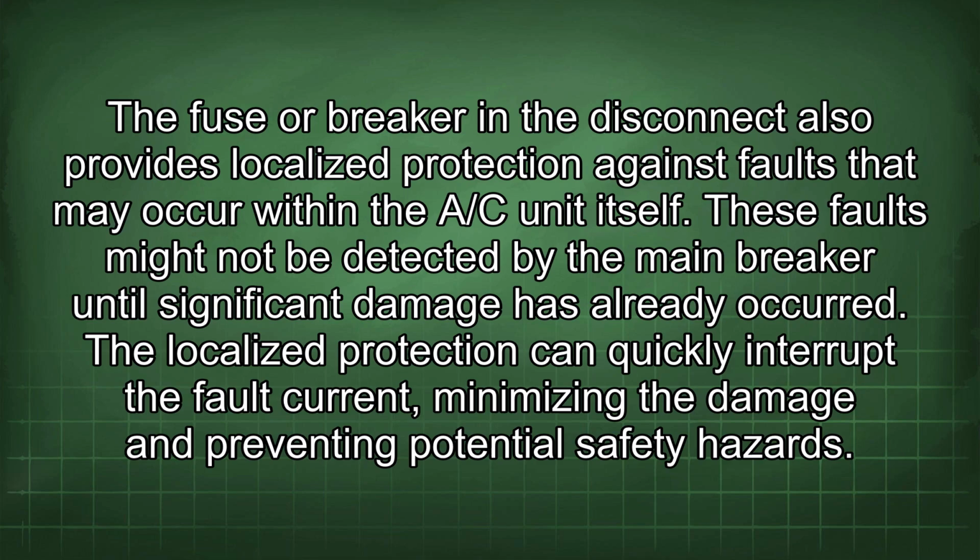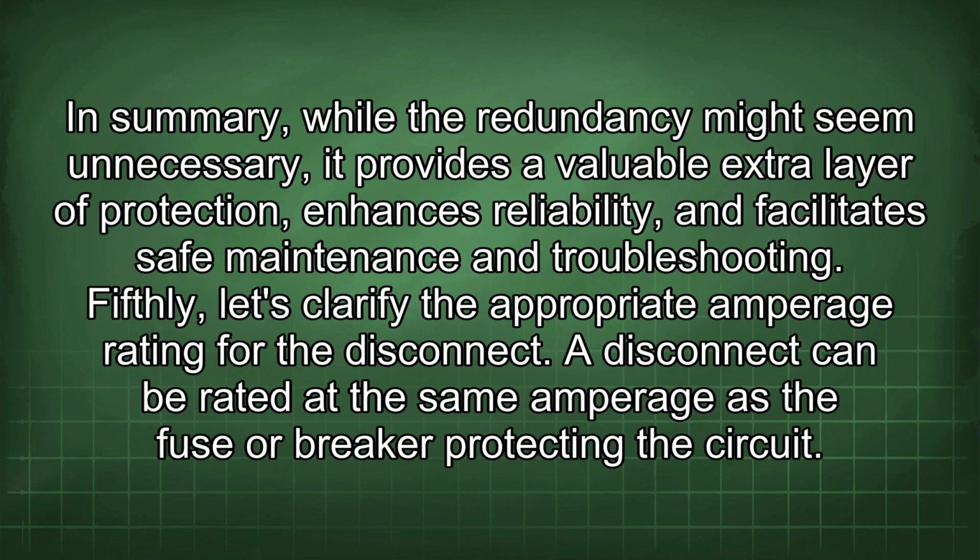The fuse or breaker in the disconnect also provides localized protection against faults that may occur within the A/C unit itself. These faults might not be detected by the main breaker until significant damage has already occurred. The localized protection can quickly interrupt the fault current, minimizing the damage and preventing potential safety hazards.